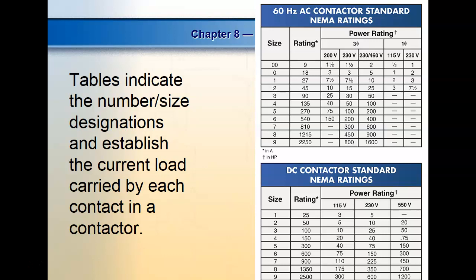What you're going to see on new ones is contactors and motor starters are going to have a size on them. I don't know what the size of ours is. We have a big one over here. The size tells you which horsepower motor you can run on the different voltages. So notice if the voltage goes up, the horsepower goes up. If the voltage goes down, the horsepower goes down. And why is that?